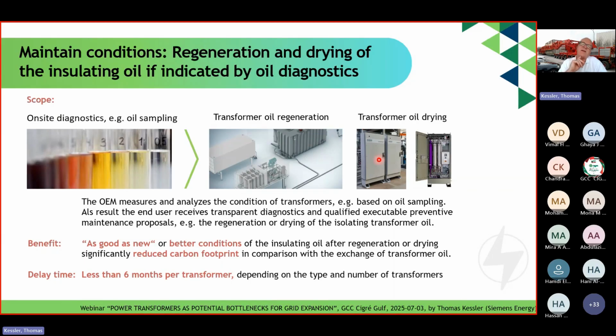What needs to be said is that both processes, transformer oil regeneration and transformer oil drying, can be executed on the energized transformer, so there is no need to shut it down. The benefit of this exercise is that after regeneration and drying, the transformer oil is in as good as new, or better, condition. Also, the carbon footprint is significantly reduced compared with exchanging the oil.